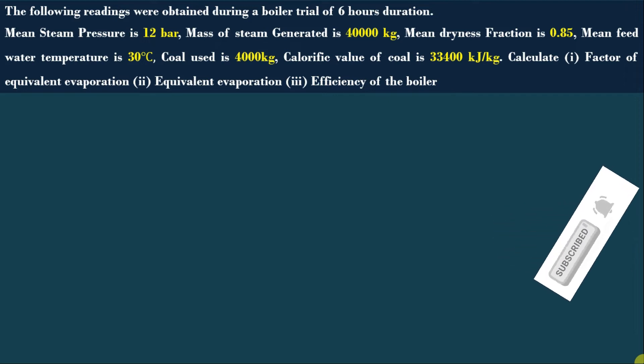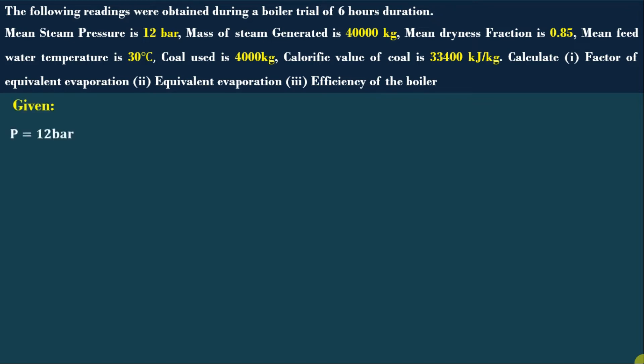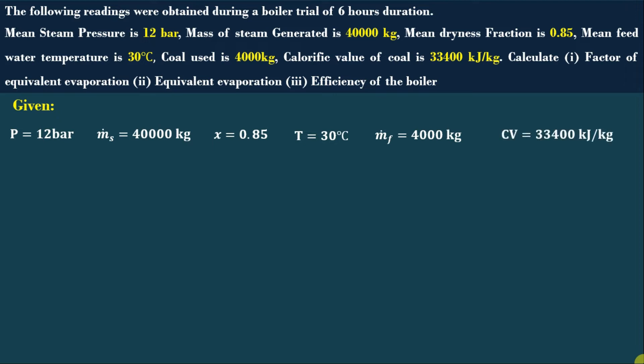The following readings were obtained during a trial of 6 hours duration. The mean steam pressure is 12 bar. Mass of steam generated is 40,000 kg per 6 hours. Mean dryness fraction is 0.85. Mean feed water temperature given to the boiler is 30°C. Coal used in the boiler is 4,000 kg. The calorific value of that coal is 33,400 kJ per kg. We need to find out the factor of evaporation, equivalent evaporation, and efficiency of the boiler.